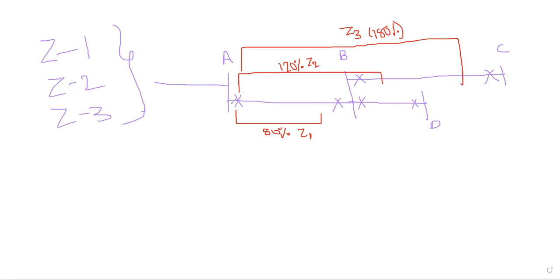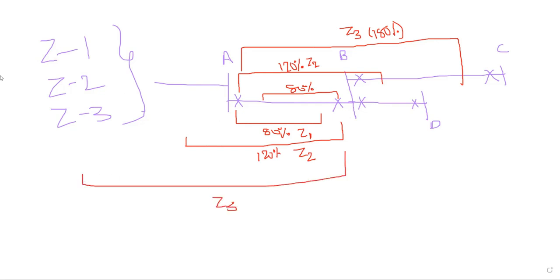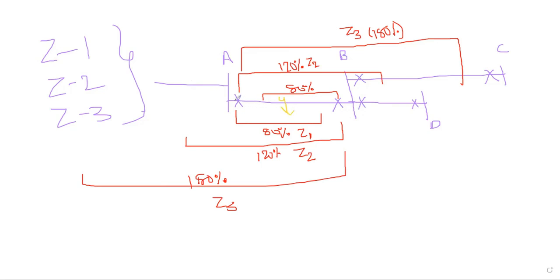And in the similar case, this is the line I am protecting. Similarly, for B, there is a breaker and a relay. This is the Zone 1 protection, 80%. 120% of the line comes under Zone 2. Zone 3, 180%. So in general, for this breaker, if a fault occurs in this region, then it is Zone 1 for this A breaker. If a fault occurs in Zone 1, the breaker will trip instantaneously. For Zone 1, the breaker will trip instantaneously.